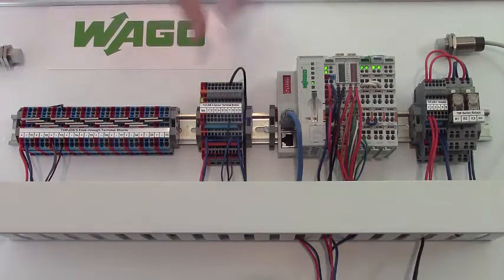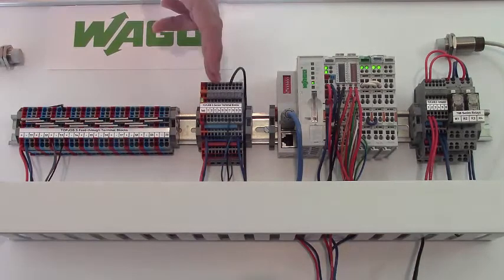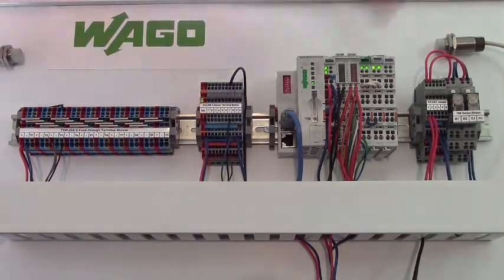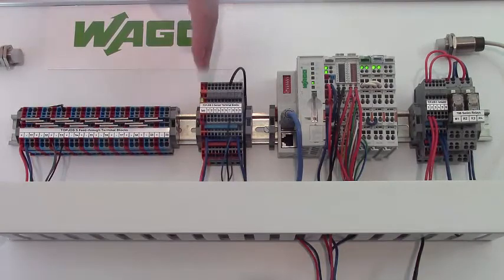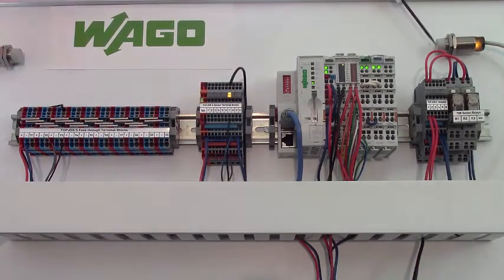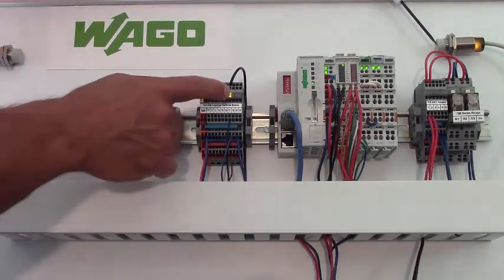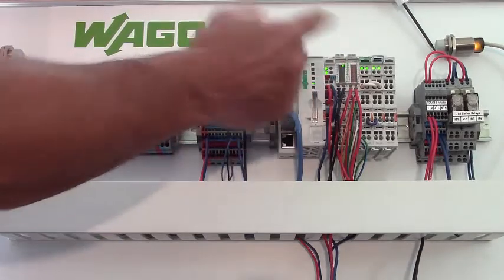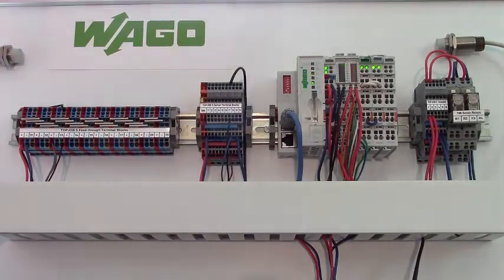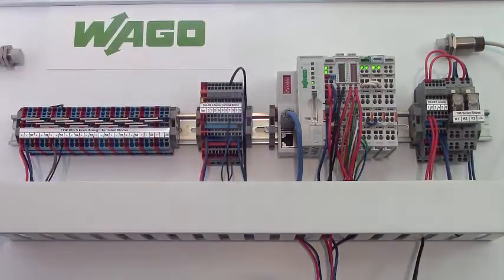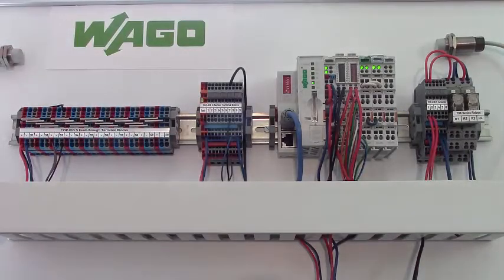If the sensor signal is present from here to the proximity sensor, then we know that part of the circuit is good. And if it wasn't present, we look at the PLC and there wasn't a signal input coming in, then we know that there's a problem between the two or it could be a problem with the I/O module, for example.